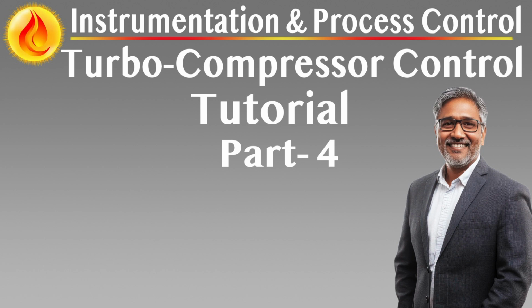All field instruments associated with the TCCS are fully aligned with the control philosophy, piping and instrumentation diagrams, P&IDs, and the general specification for instrumentation and control for package equipment. Scope of supply and integration, complete field instrument package. The TCCS vendor is responsible for supplying all instruments located on the compressor skid as defined in the project P&IDs and equipment data sheets. Wiring and termination.